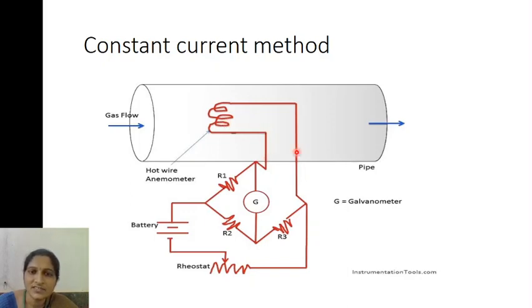The ends of this hot wire anemometer are connected to one of the arms of the Wheatstone bridge, so there is unbalancing of the bridge. Because of this unbalancing of the bridge, the galvanometer deflects. Here, the current is maintained constant and the temperature gets changed. So this is called the constant current method.